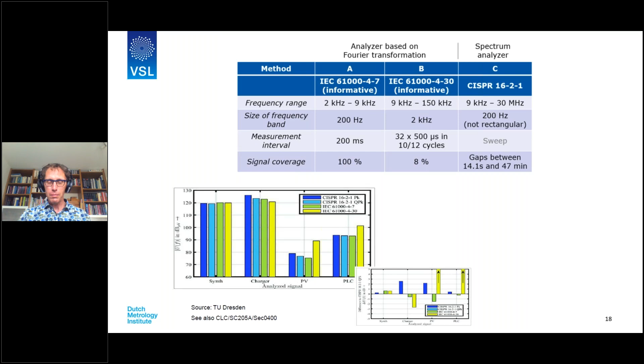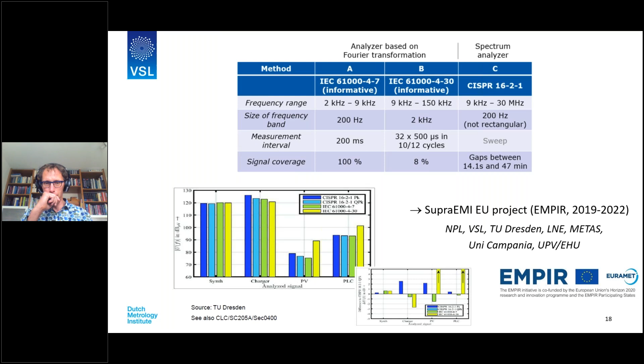These discrepancies have led to the SupraEMI project, which is on grid measurements of 2 to 150 kHz harmonics to support normative emission limits for mass market electrical goods. It provides metrological support to the IEC Subcommittee 77A Working Group 9, mentioned before, on the development of the new edition 4 of the 61000-4-30 Annex C.